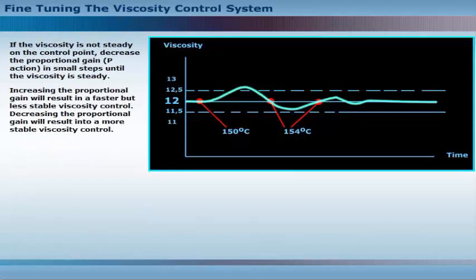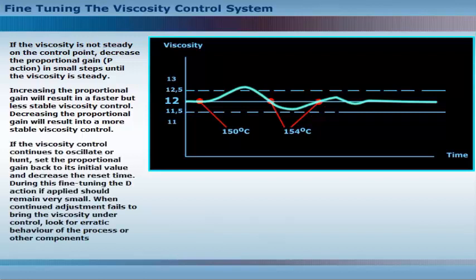If the viscosity is not steady on the control point, decrease the proportional gain in small steps until the viscosity is steady. Increasing the proportional gain will result in a faster but less stable viscosity control. Decreasing the proportional gain will result in a more stable viscosity control. If the viscosity control continues to oscillate or hunt, set the proportional gain back to its initial value and decrease the reset time.